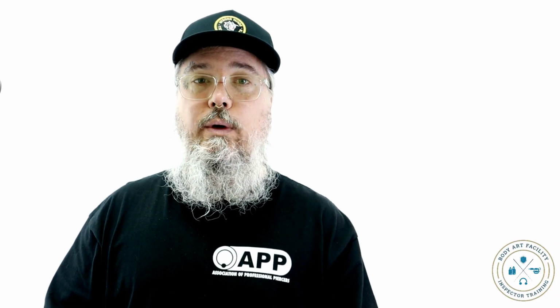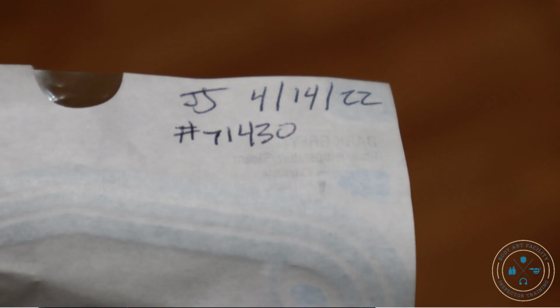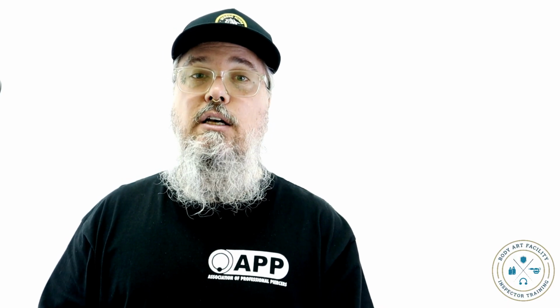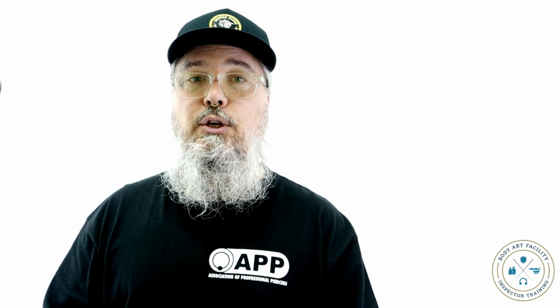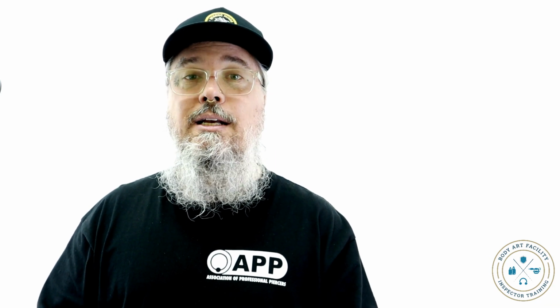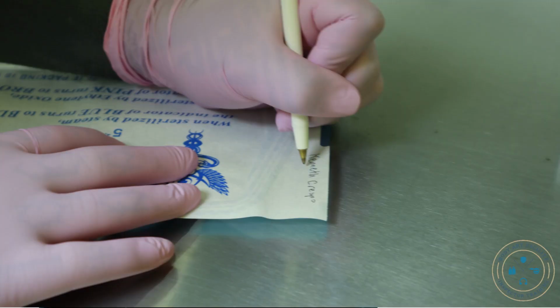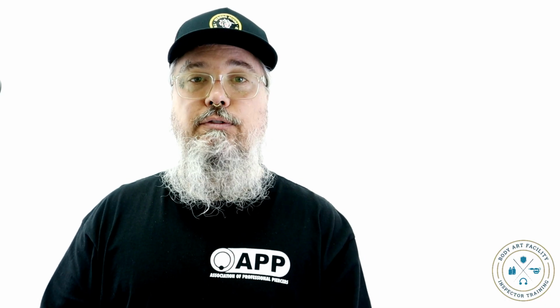Pouches must be labeled with the sterilization date, cycle number, and the operator's name or initials. This helps with traceback in the case of an autoclave failure. Unless the manufacturer has communicated otherwise, labeling should be done on the outer edges of the pouch to avoid compromising the quality of the paper. The tab used for opening the package is the best place for this.